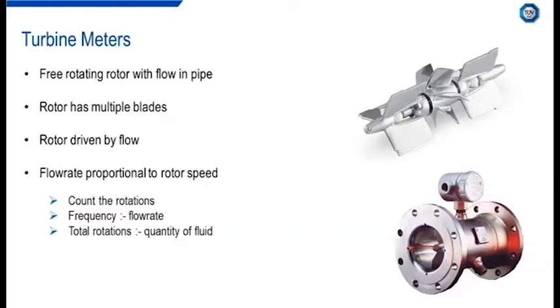Turbine meters, as I said, are available for both liquid and gas. They are, however, susceptible to disturbances in the flow profile, and so for a turbine meter, what's recommended is a minimum of 30 diameters of straight piping upstream of the meter for a fully developed flow profile for optimal performance, or use of a flow straightener.